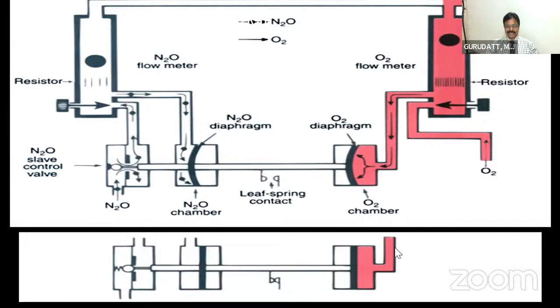You can see the diagram below. The oxygen flow, we have stopped the oxygen flow, so you cannot open nitrous oxide. That's how you can easily differentiate whether it's a Link-25 or an ORMC. In Link-25, as you start opening the nitrous oxide flow control knob, the oxygen flow control knob also rotates. Whereas in the case of ORMC, if you try to open nitrous oxide, no flow will come.